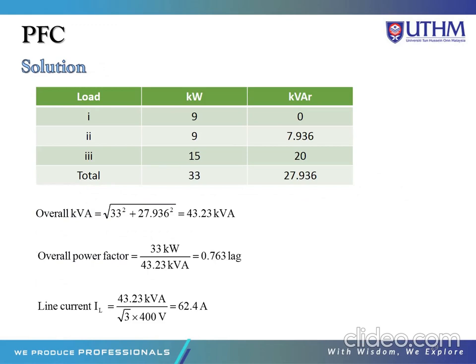This is the solution. First we have to get the P and Q for all loads before we get the total load. By putting all the values in the table, we get the values of P and Q for the three loads. The total for P is 33 kilowatt, and this is the value of kVAR. Then we have to calculate the total kVA. To get S total, we use the formula square root of P squared plus Q squared. By using this formula, we get the overall kVA, which is equal to 43.23 kVA.